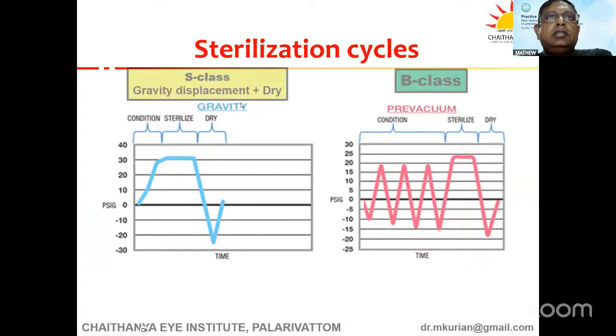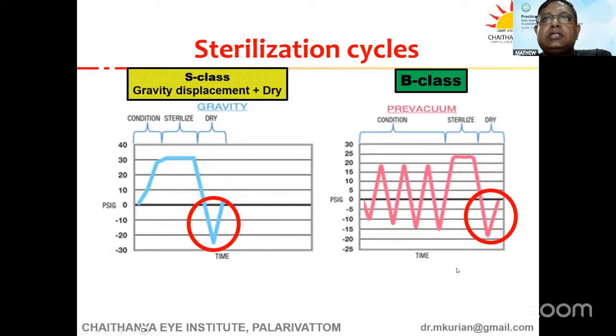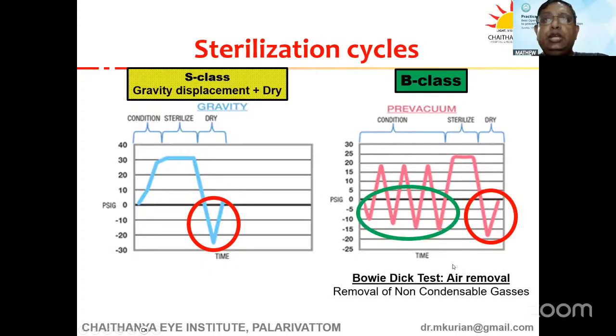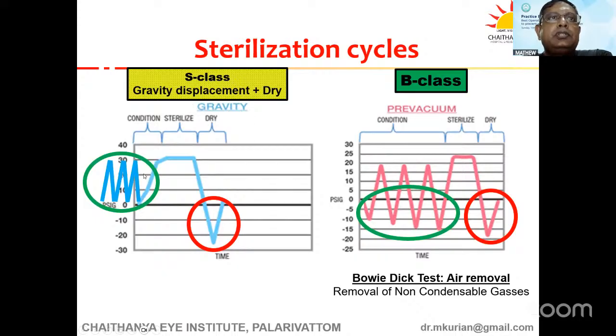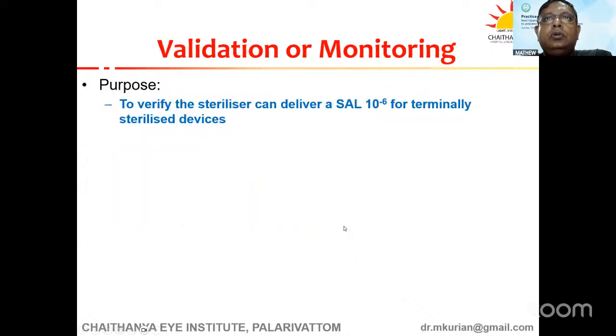So what does this mean? In S class, you have the gravity displacement. There is a dry cycle. That is this one over here. At the end of the steam charge, we have an opportunity to dry that one. B class also has that one. And in addition to the S class, what it does is you have pre-vacuum cycles where the air removal is completed, and this is validated by the Bowie-Dick test. Sort of equivalent thing can be done in the S class by having positive pressure charges, but it is not as effective as having the negative vacuum to remove the air.